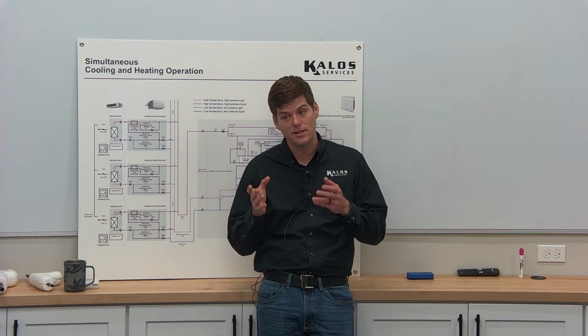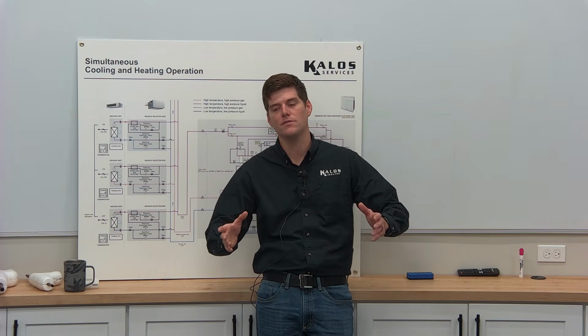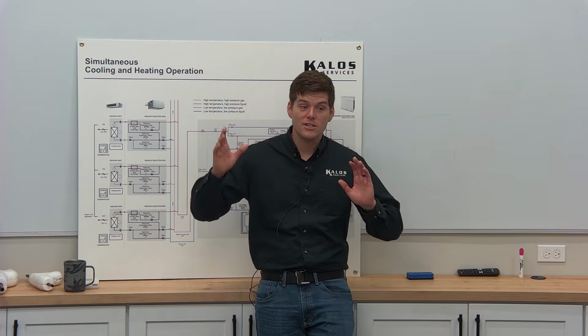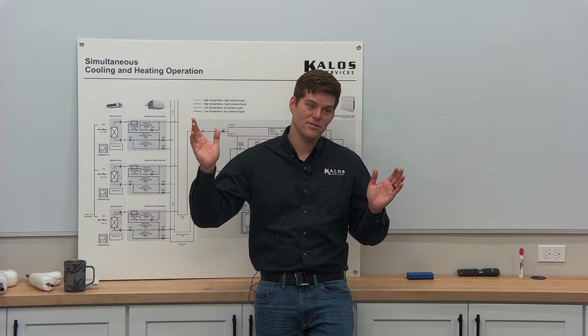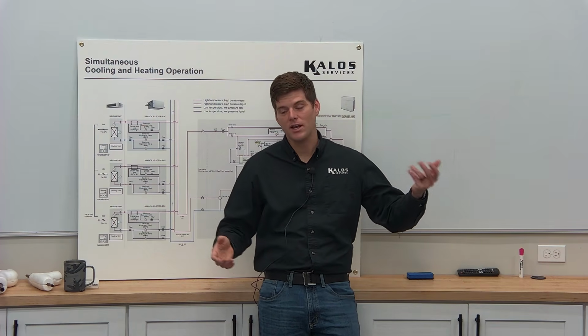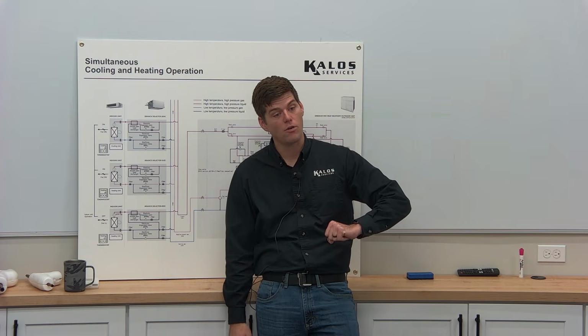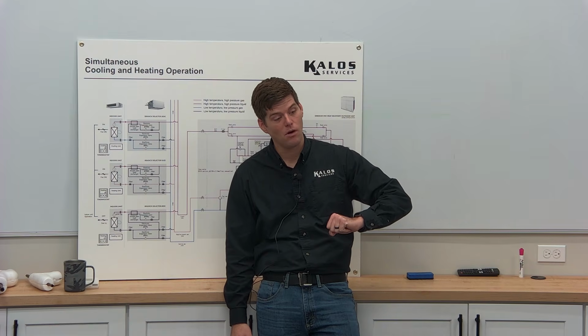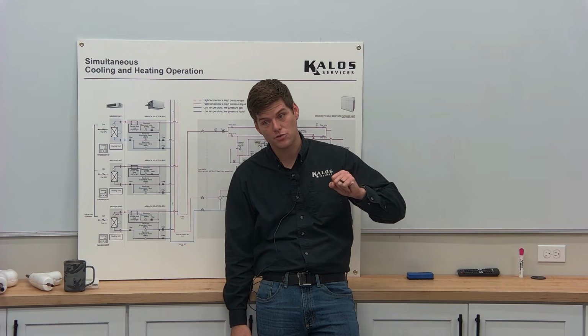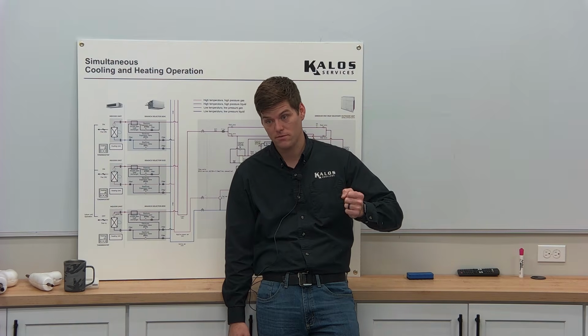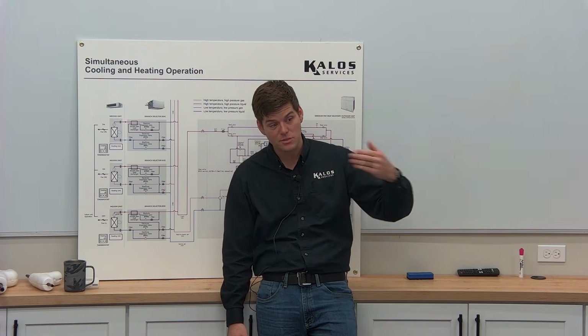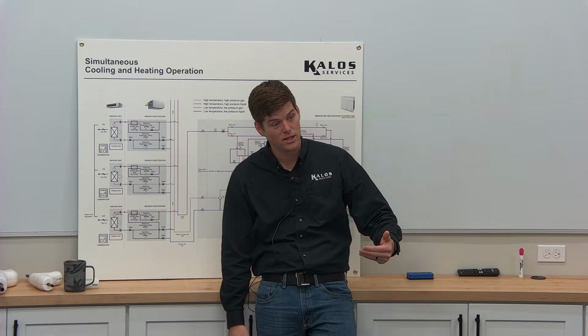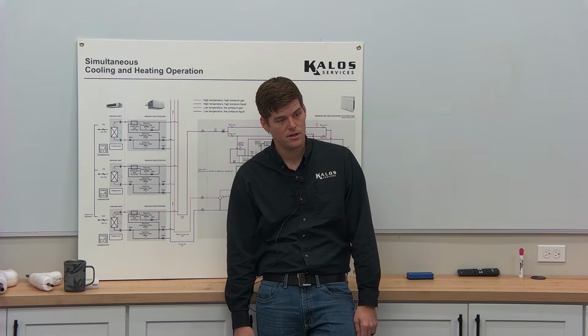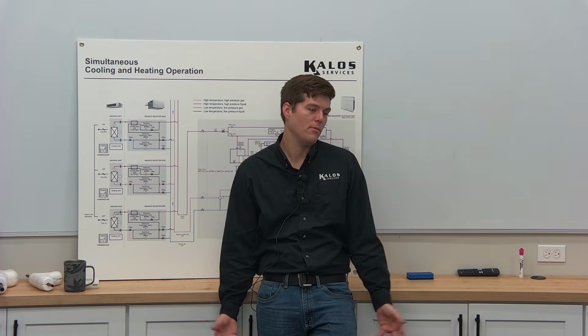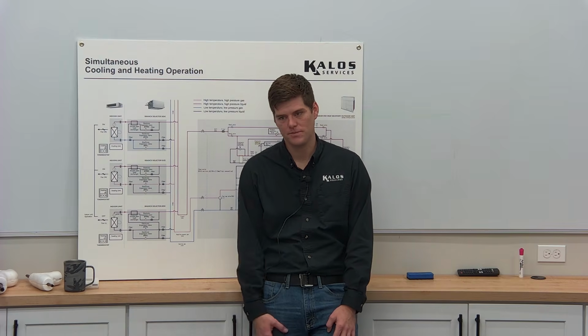And so they're like fancy solenoid valves because they soft open and they soft close. Everybody has seen a house or been in a house where you shut the water off quickly and the pipes hammer in the wall. The same concept is true in chilled water. The same concept is true in refrigerant, right? If something is moving at a high rate of speed through something and you close it quickly, it can create noise. It can also create turbulence, vibration, nuisance calls.